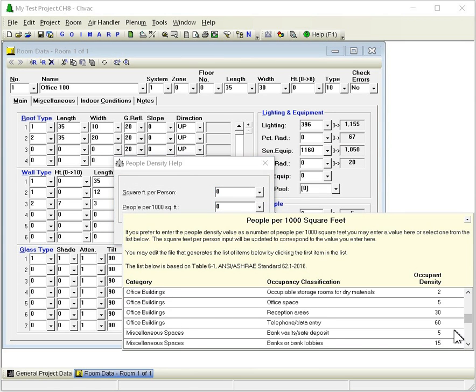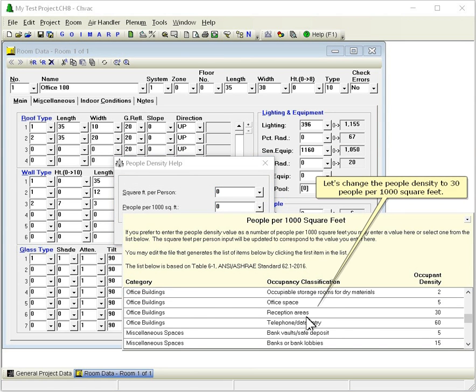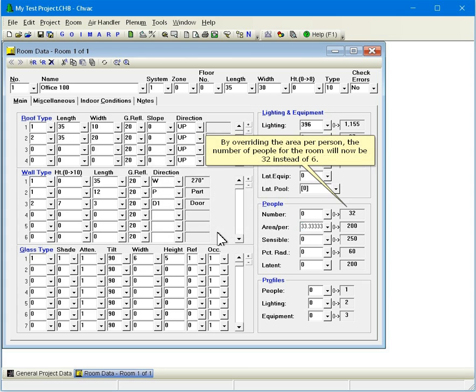Let's change the people density to 30 people per 1000 square feet. By overriding the area per person, the number of people for the room will now be 32 instead of 6.